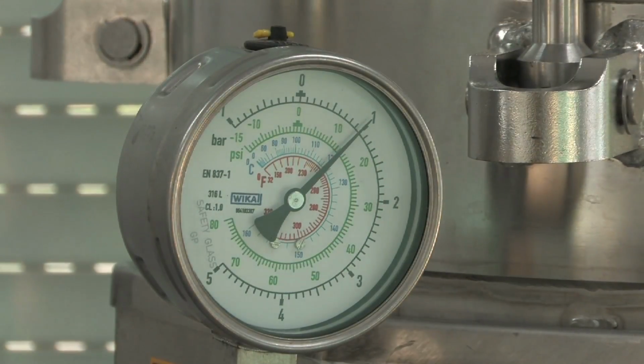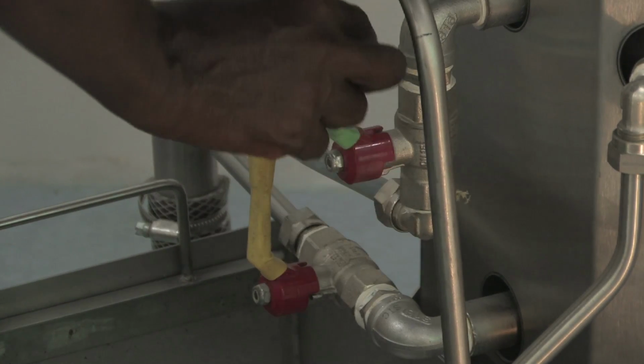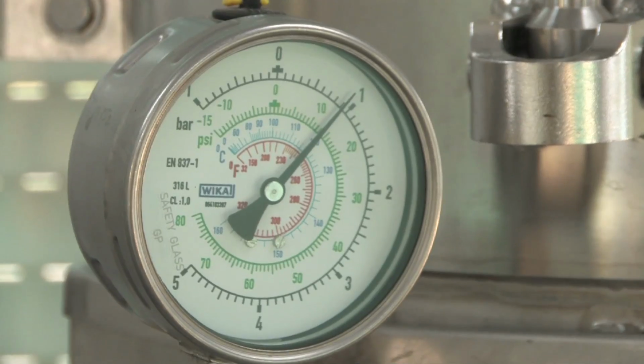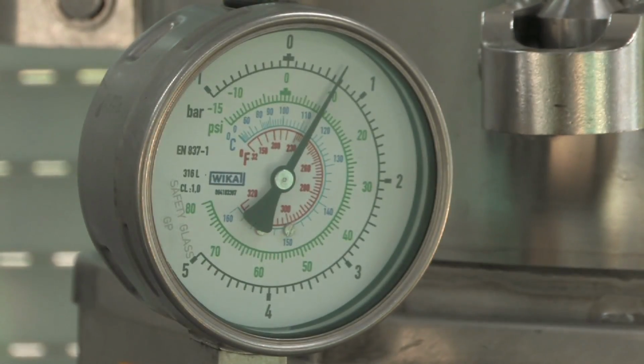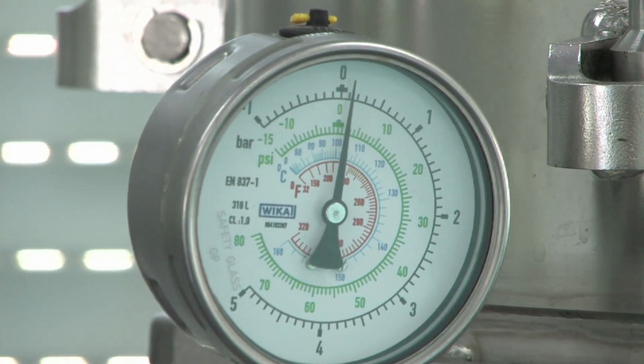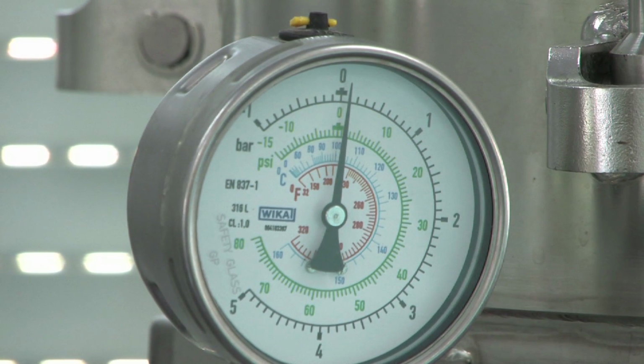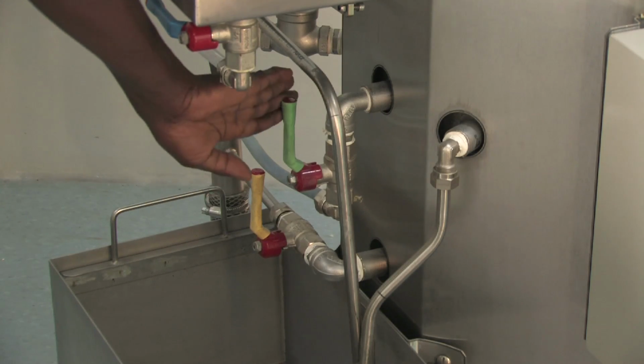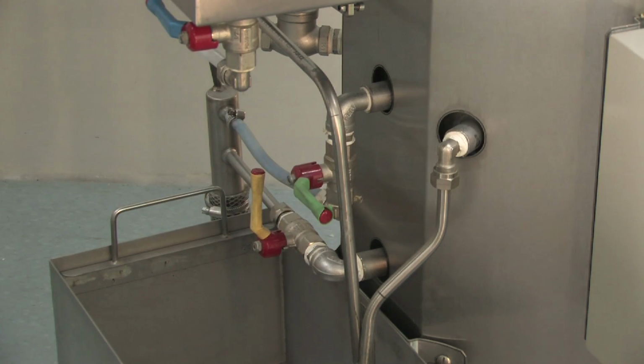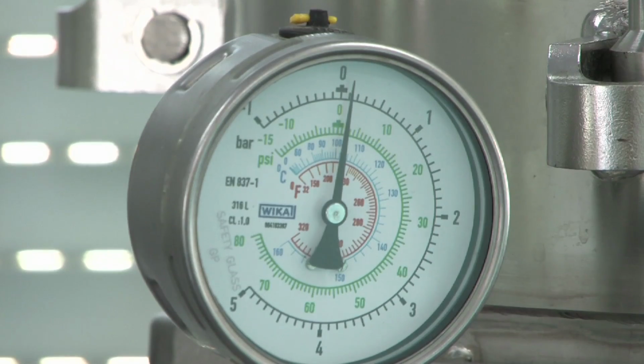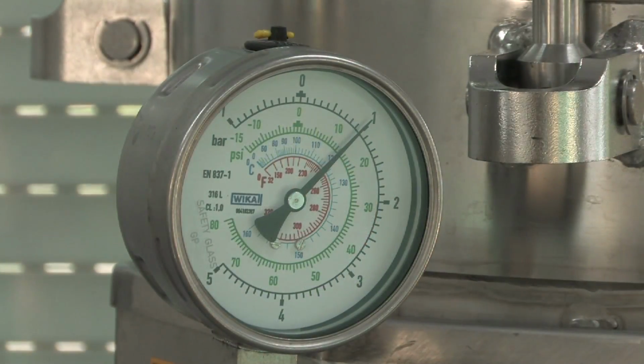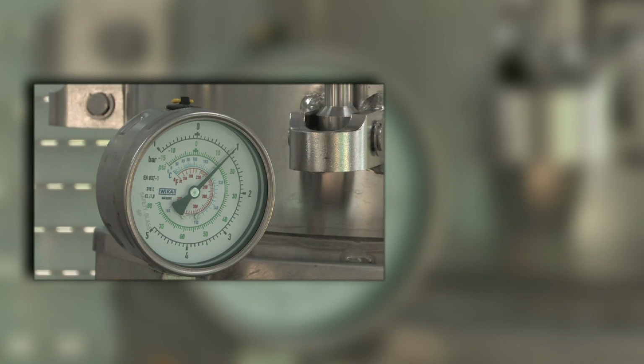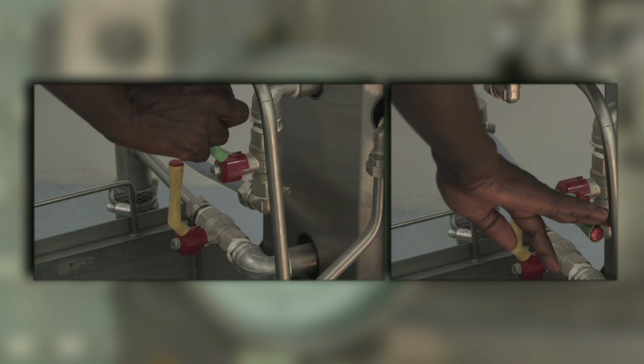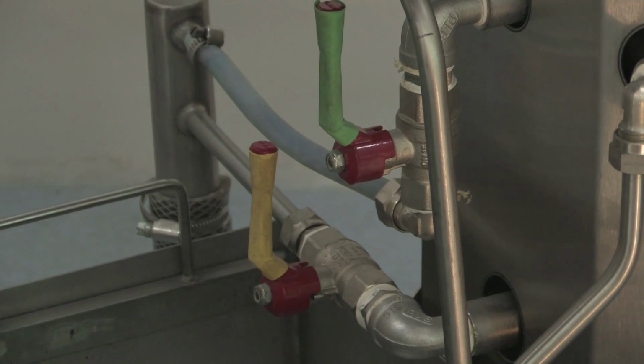When the pressure gauge indicates 1 bar, reopen the green valve to get rid of the pressurized air that has accumulated in the bottom of the autoclave. The pressure then falls. Do not let it drop below 0.1 bar. Reclose the green valve and let the pressure rise again. Repeat this operation 3 times to ensure that all of the air in the autoclave has been removed. Note, during the 3 successive purges, always keep the pressure above atmospheric pressure, at least 0.1 bars, to ensure that no air goes back into the autoclave.